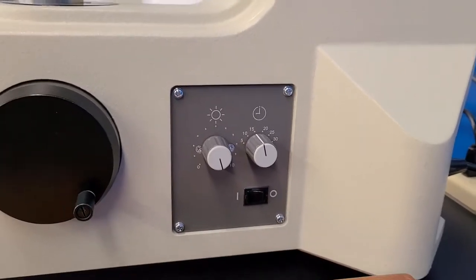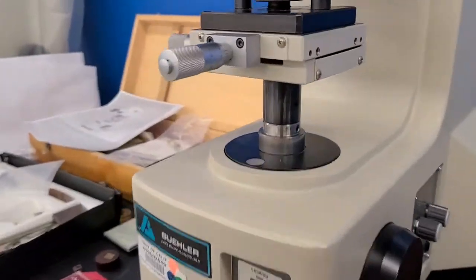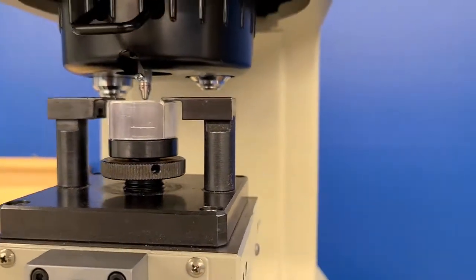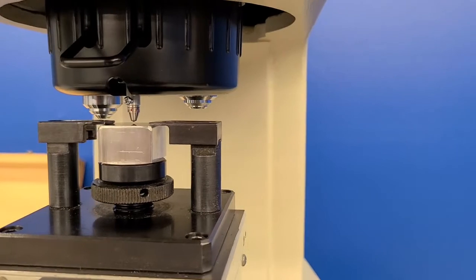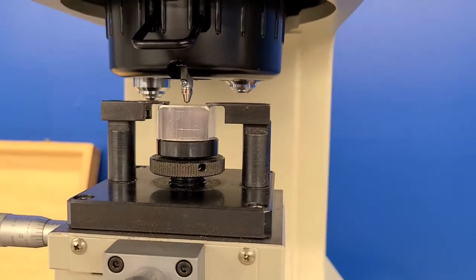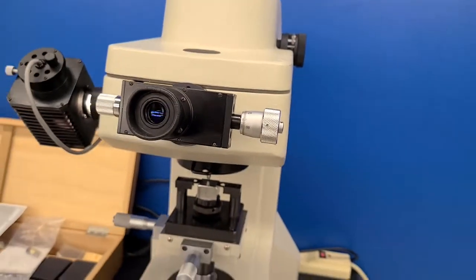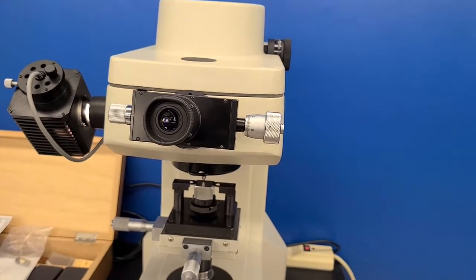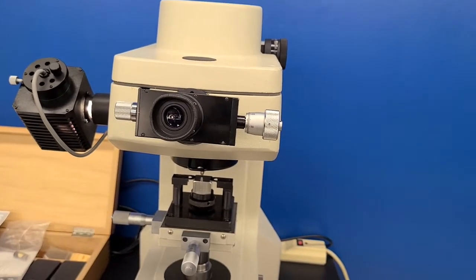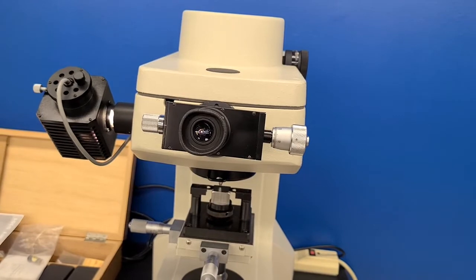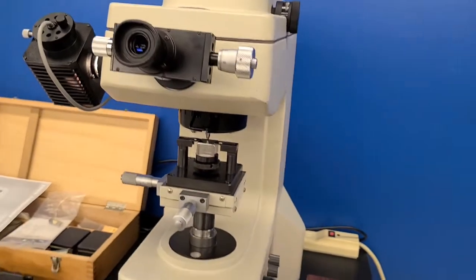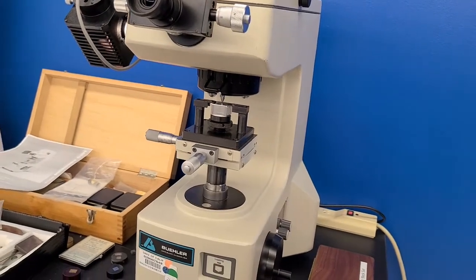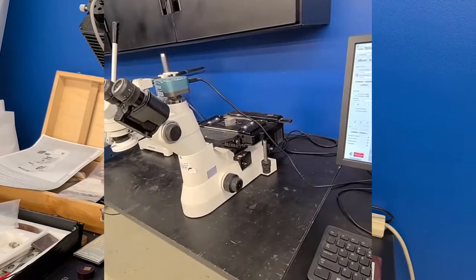So what it does is it applies 15 grams of force on this indenter, holds it for 15 seconds, and then comes out. You can see the tip has come out of contact. So we can now look into this microscope and measure that indent. I can't really get a good image of this on this equipment, but what I'll do is make a few indents and take them over and show you them in a different microscope.